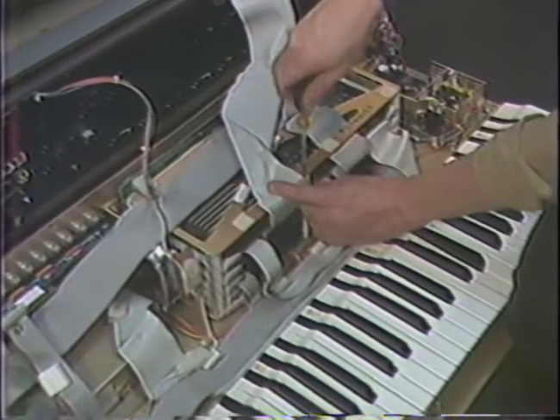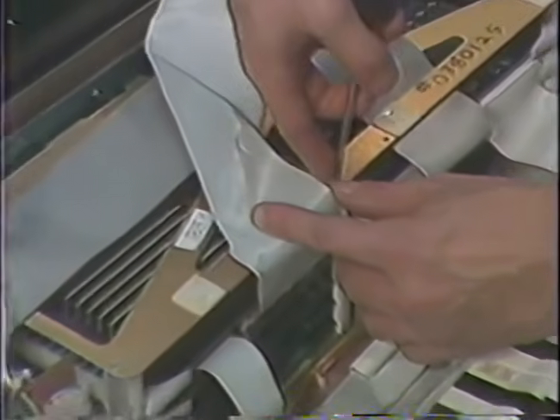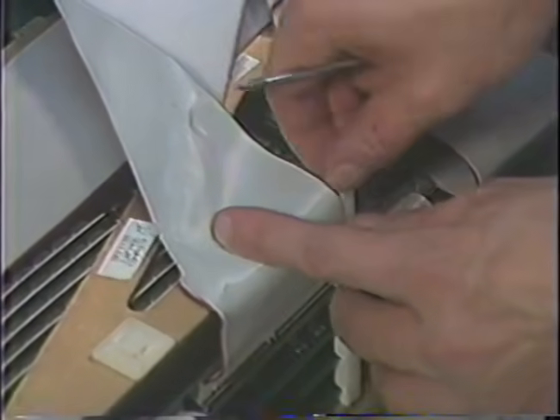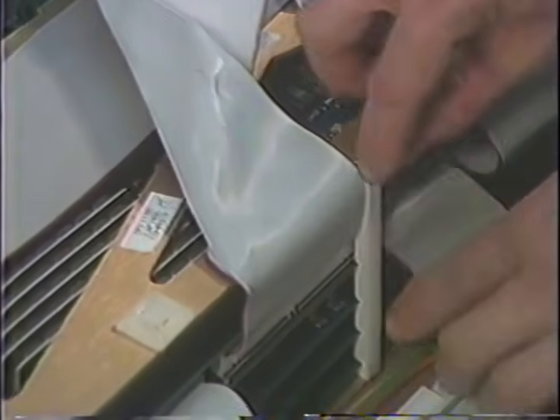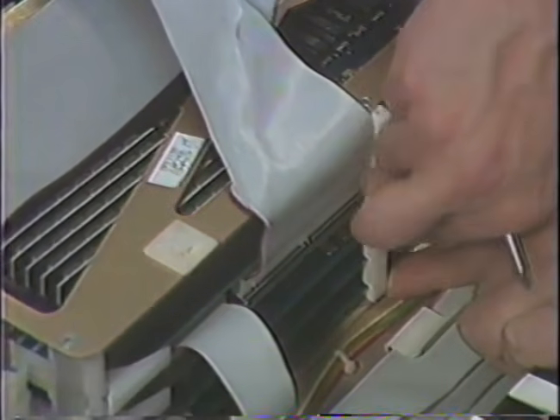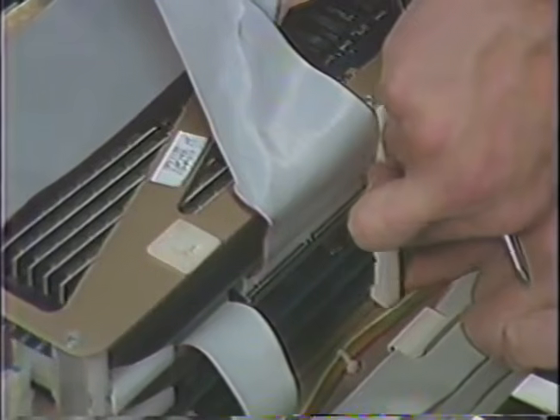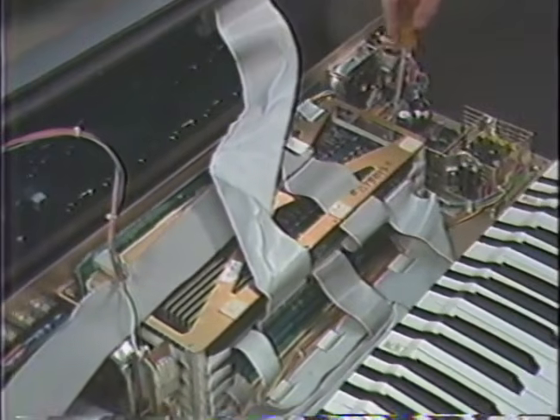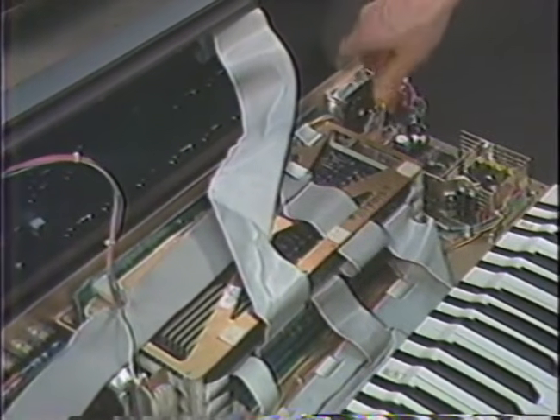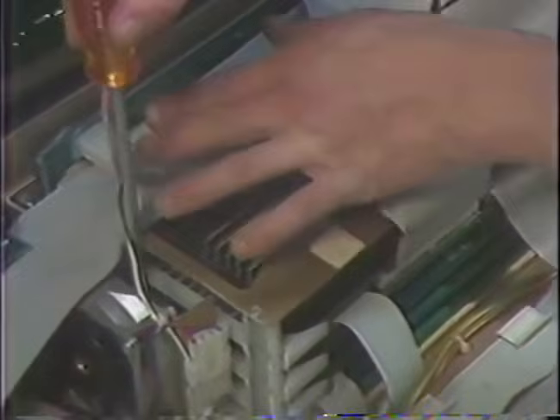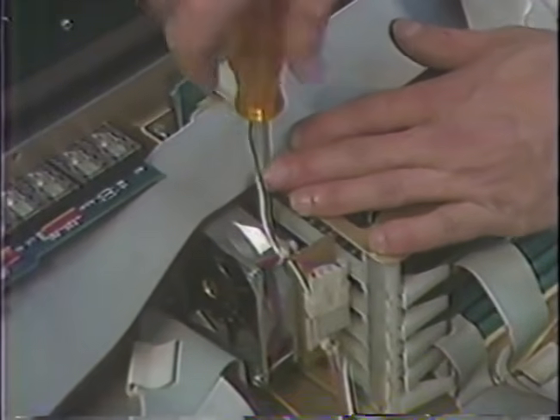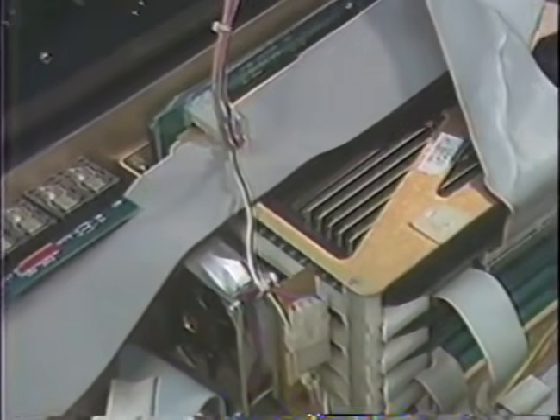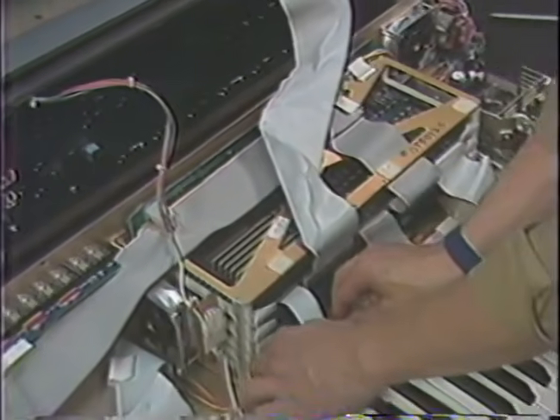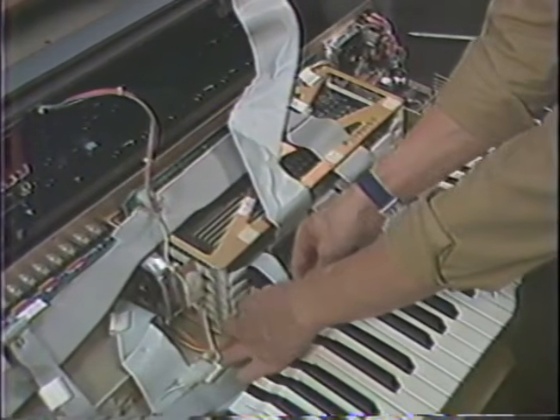There is a card retainer that is secured by 1 screw from the top. This will need to be removed to gain access to any of the 5 PCBs. The retainer can be released by applying pressure on the base of the card cage. The card cage is secured by 2 screws to the base. If removal of any of the bottom 3 boards is required, these screws need to be released and the cage tilted upward. Cables will need to be undressed, giving access to the tilting.